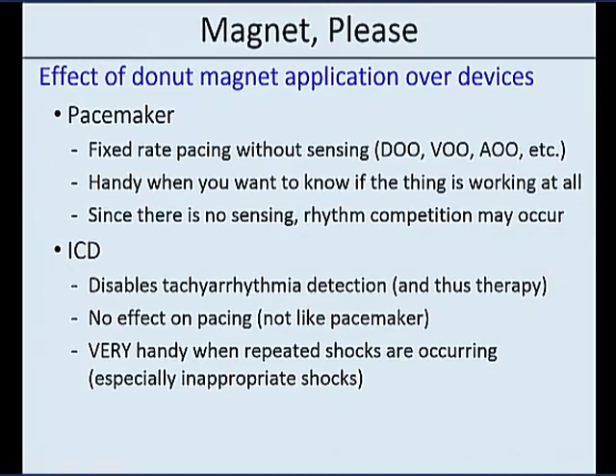So if you've got somebody who you don't know if they're oversensing something, then you can just slap a magnet on it and it'll start pacing anyway, and you can see whether the thing is even capable of responding, whether the battery's dead or anything else. It's not sensing any rhythm, and so you may end up inducing atrial fibrillation or some short episodes of VT with poorly sensed or non-sensed complexes.